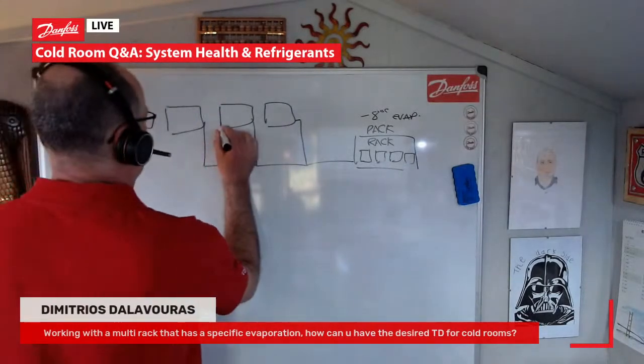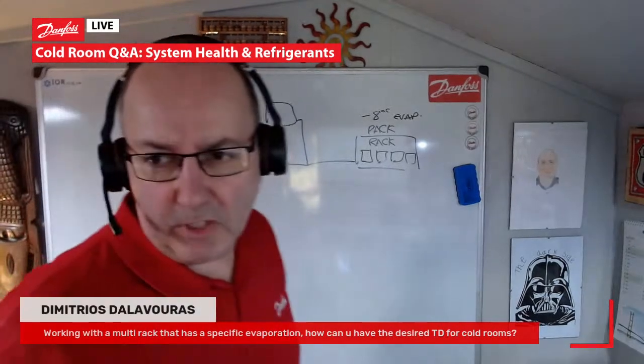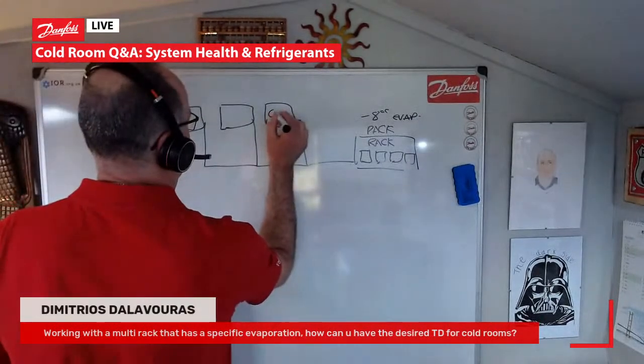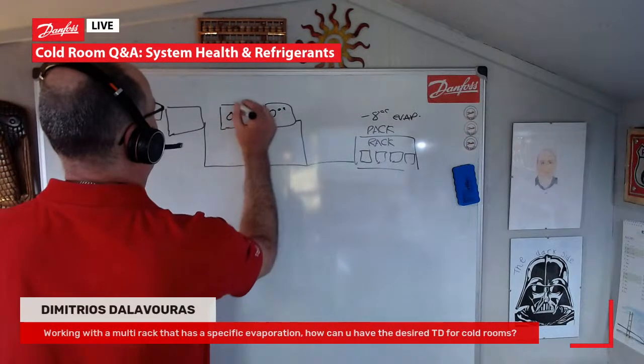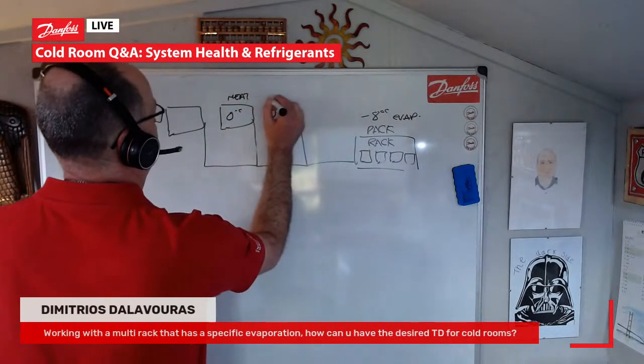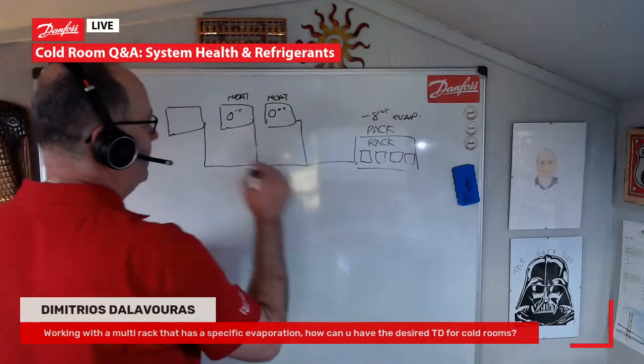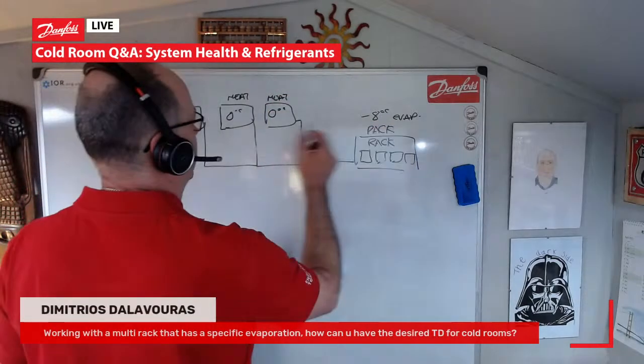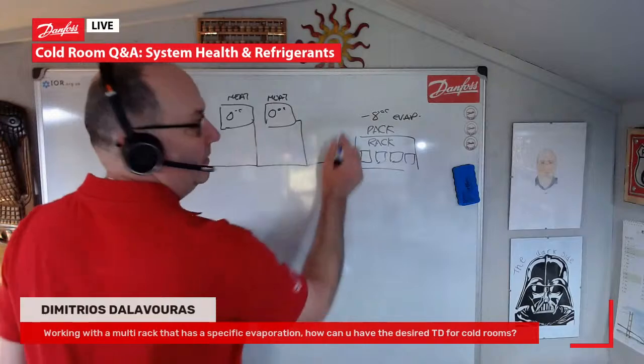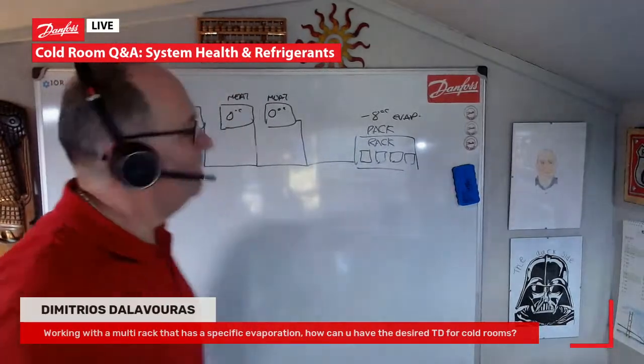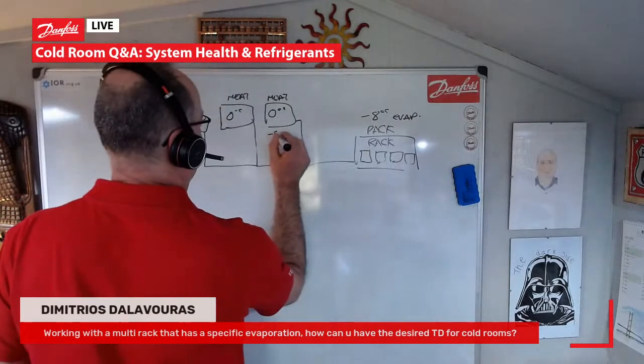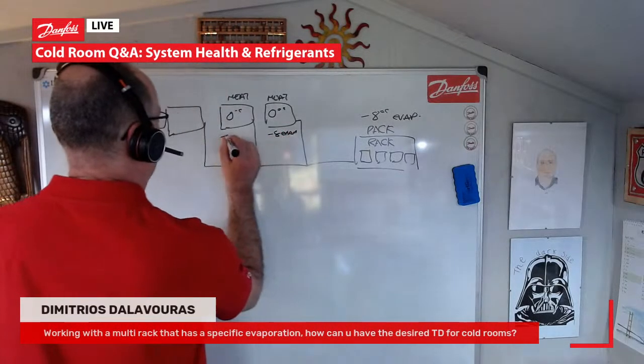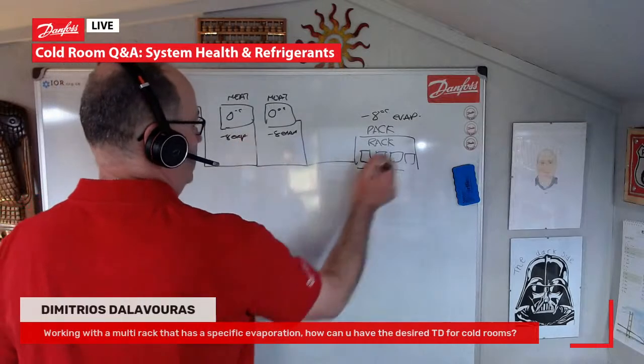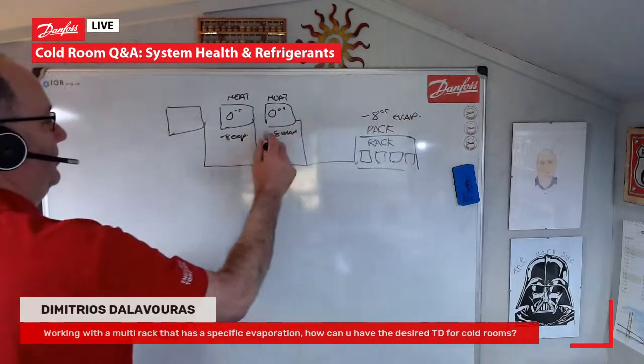So, yeah, in simple terms, if you wanted the meat cabinets at 0, so they'd have 0 degrees C. Let's say we've got a couple of them, so they're the meat cabinets. And you're evaporating at -8, so we want those at 0, and you wanted an 8K TD, so those are evaporating at -8, which is fine because the rack's doing -8 and they're evaporating at -8.